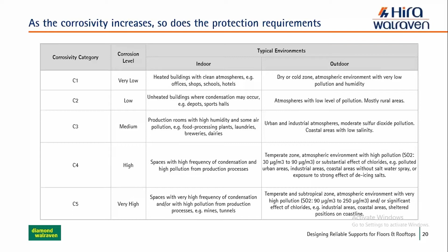What we usually see for outdoor installation, especially around this region, is C3 and C4, sometimes mixed on the same building, sometimes just one. For outdoor settings we're talking about urban and industrial atmospheres, coastal areas with low salinity and without saltwater spray or strong exposure to de-icing salts, which is not the case here. There's some effect of chlorides and a bit of pollution as well. Depending on where the building and installation are placed, there can be more or less pollution or industrial residue in the air, and this will greatly impact corrosion later on.